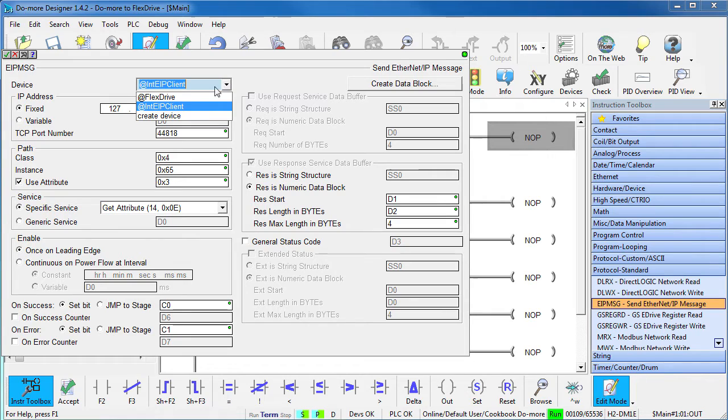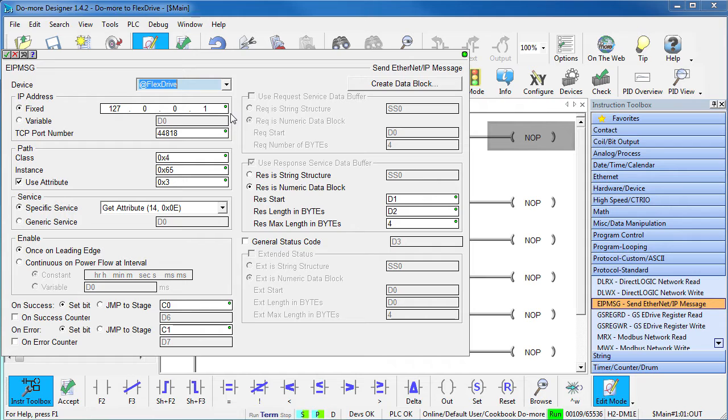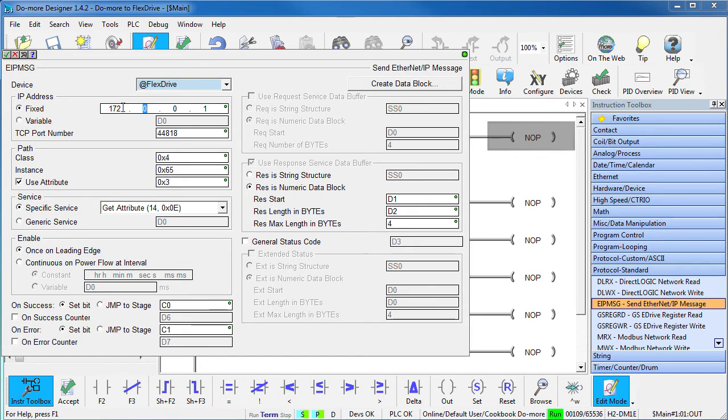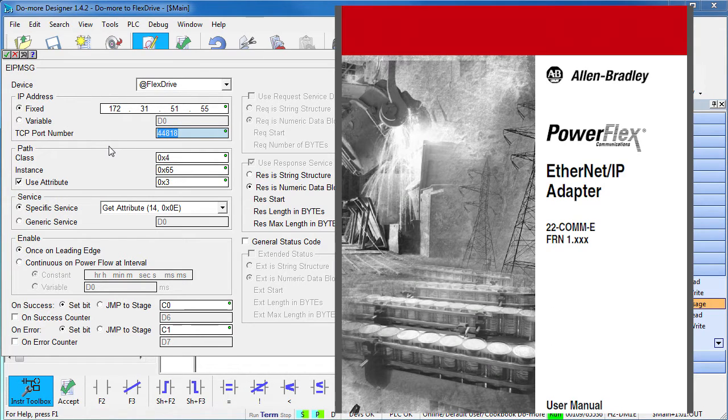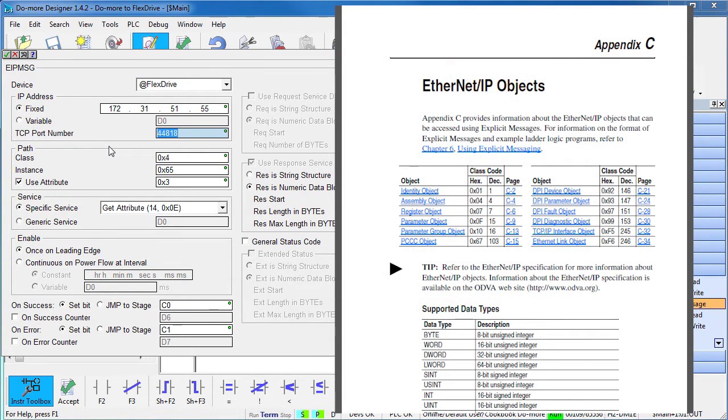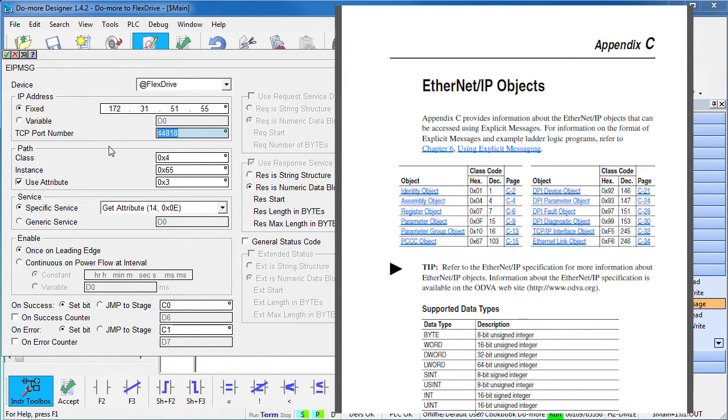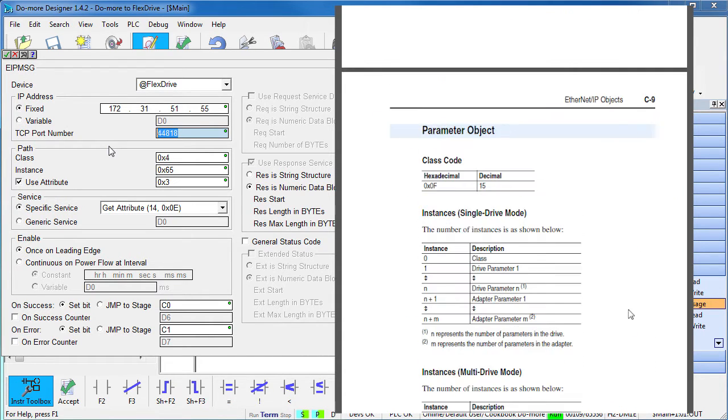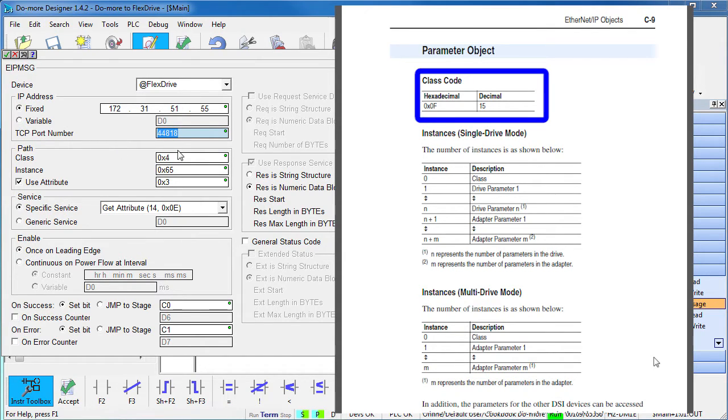We want to talk to our PowerFlex device. Remember, that device, which is a lot like the drivers you have on your Windows PC, manages the hardware for you. It takes care of all the handshaking, the error checking, the memory allocation, etc., so you don't have to mess with any of that. It makes your life easy. We'll enter the device's IP address here. And we have a direct connection so the default port number is fine. For the rest of this, we just look up the answers in the PowerFlex 40's Ethernet IP adapter manual. In Appendix C, we see all the different classes available. We want the parameter class so we'll scroll down to page C9. Here is everything we need to know about how the parameter information is organized. The class number is 15. That goes here.